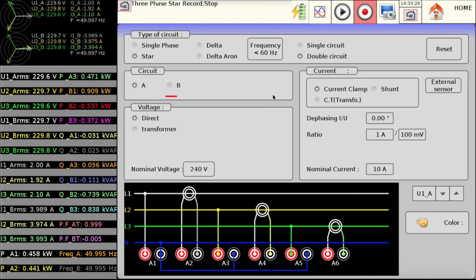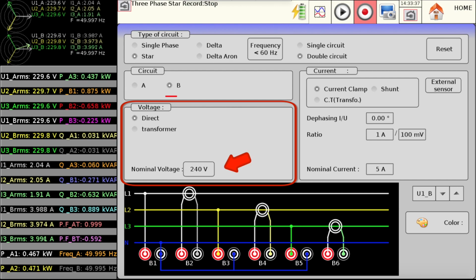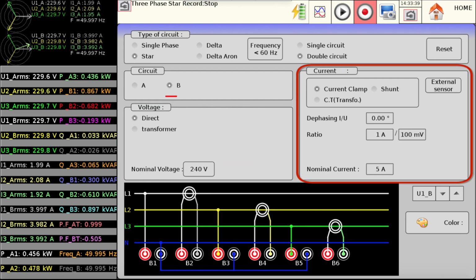Now we are going to configure the circuit B. This circuit also has a direct voltage with a nominal voltage of 240 volts. The current will be measured with a clamp, but this time we won't enter a transformer ratio. For this example, we use a SP221 clamp from Sefram.